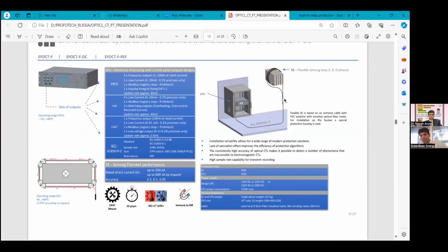Here is the flexible CT, which is installed on a bus bar. These are the outputs: frequency output, milliampere output, fast output, and IEC 61850-9-2 output. Here is shown the EPU unit, which is one type of processing unit. From that you will get the desirable outputs. The sensing element can measure up to 350 kiloampere, and up to 600 kiloampere by request. Accuracy class 0.2, 0.1, 0.005.